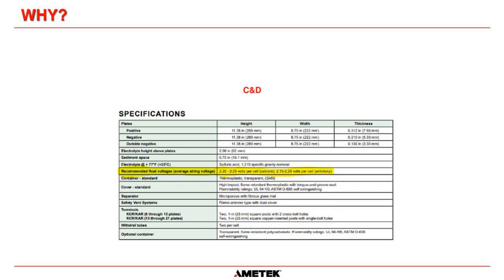Now, if your room isn't going to be in a temperature controlled environment, yes, I suppose temperature compensation is going to extend the life of your battery to a certain extent. And really all it's doing is changing for the seasons. When it gets hot in the summer, it's going to reduce the voltage, and when it gets cool in the winter, it's going to increase the voltage. But if you live in a temperate climate, let's say where the range of temperature is between 60 and 80 degrees Fahrenheit, temperature compensation isn't going to get you much, to be honest.